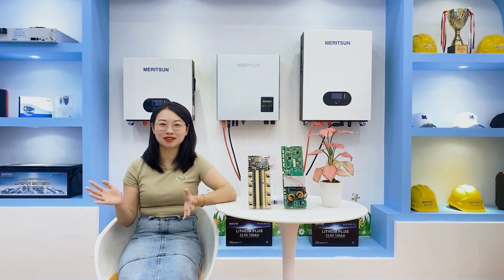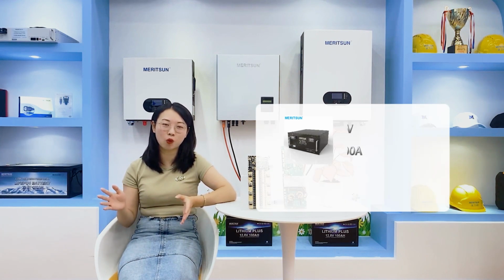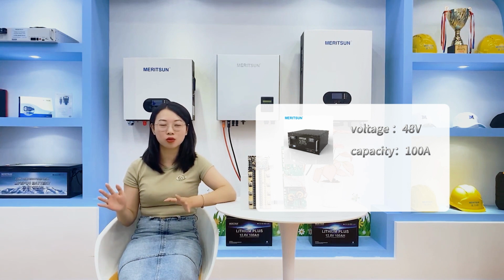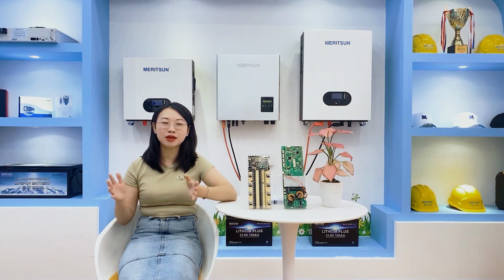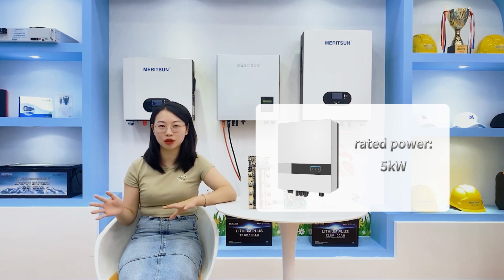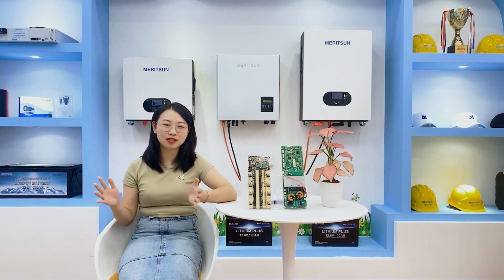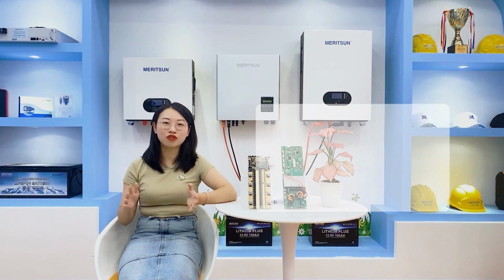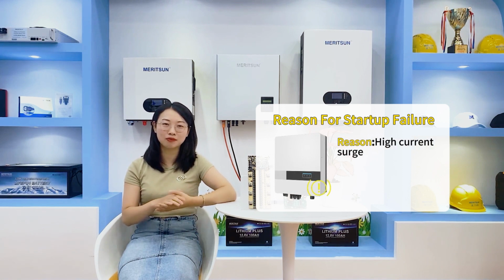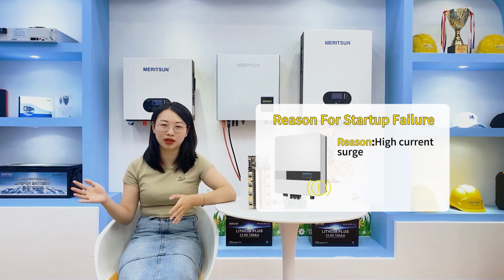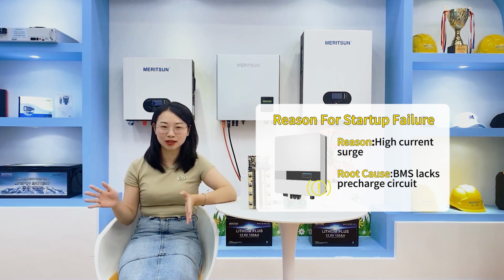Recently, our customers consulted us a technical question. He has purchased a 48-volt 100 Ah battery with 100 amp BMS, believing it could power an inverter rated below 5 kW. However, they encountered issues, the inverter failing to start. Upon investigation, we found that the failure to start may be due to the impact of large current, and the root cause is the absence of a pre-charge circuit in the battery assembly BMS.